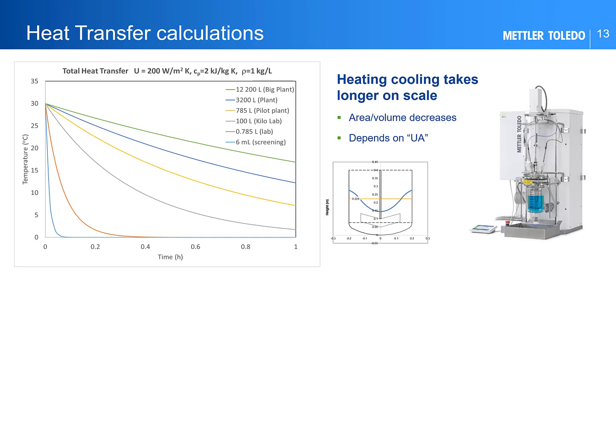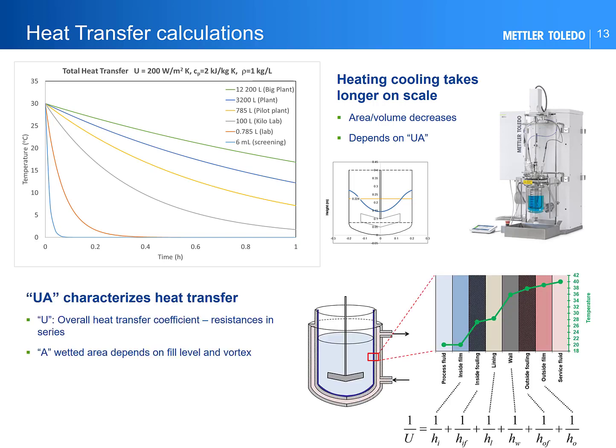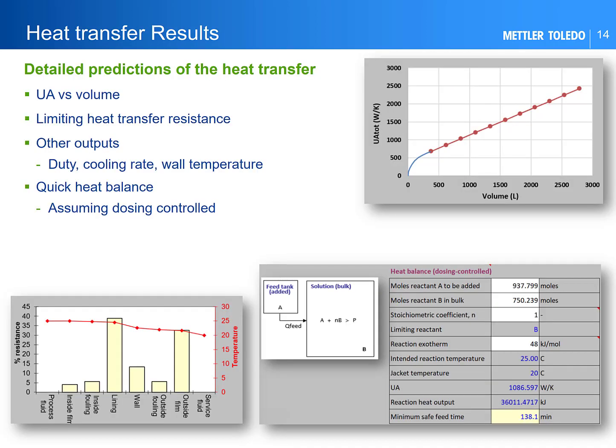The toolbox allows a calculation of the UA, which comprises the wetted area from the geometry and amount of liquid, plus the vortex which can create some extra area, and the U value which can be estimated from engineering correlations. This U value is a series of resistances through the vessel wall and the fluid films either side of the vessel wall. The calculation allows you to see which heat transfer resistance is limiting — for example, it could be inside the vessel wall or on the jacket side — and this will allow you to see if increasing the agitator speed will improve heat transfer. You can also see the UA versus volume, and get other outputs like wall temperature, cooling and heating rate, etc.